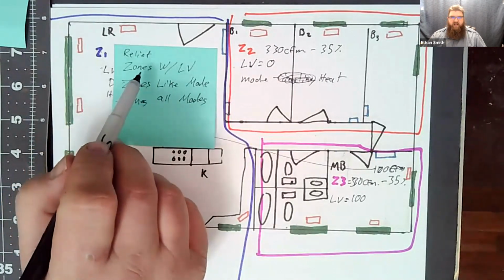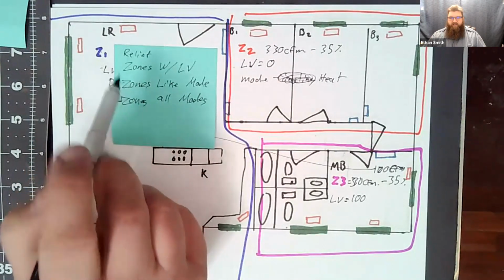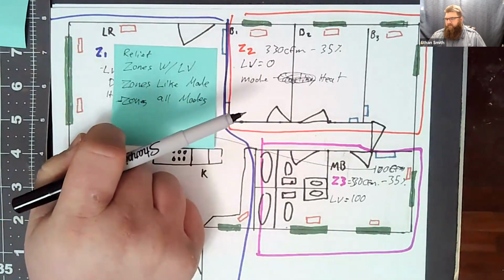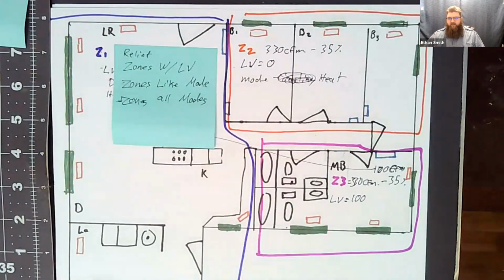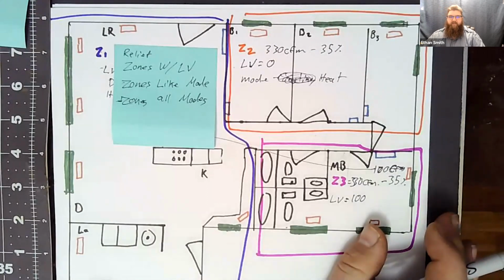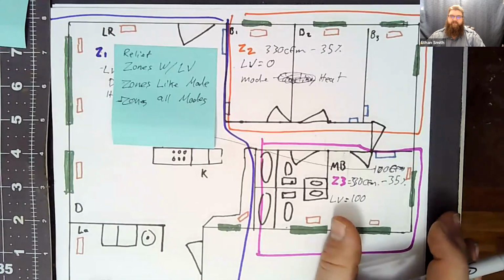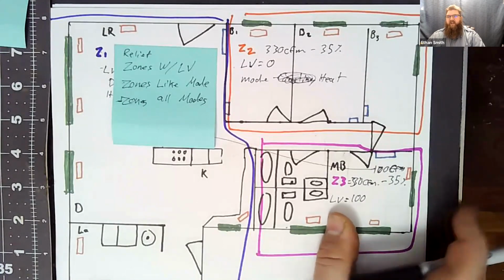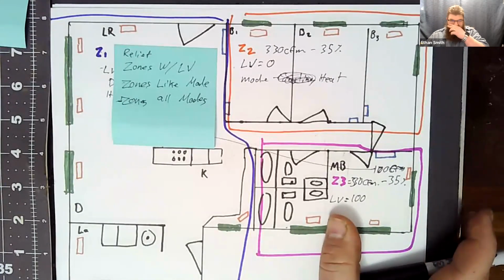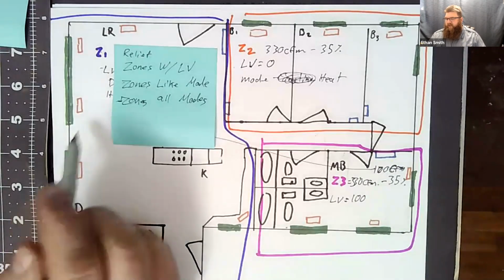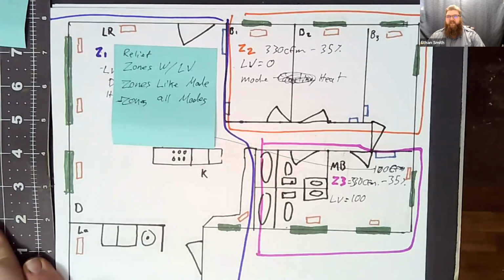Okay. Where this happens is where guys try to put too many zones on too small of a system. And while a lot of these intelligent zoning systems will handle 8 zones, I'm going to tell you right here, right now, today, guys, it's a bad idea. Even if you've got a 5-ton unit, an 8-zone system is going to have a lot of problems. It's going to require a lot of tuning if it ever works at all. Okay. I would advise most people doing zoning maximum of 4 zones. Because once you start getting over 4 zones, you're almost guaranteed to have non-voting zones at that point. Your zones are getting really small. It starts to create lots of excess air problems, and your relief strategy is going crazy trying to compensate for you. But it's gonna struggle.